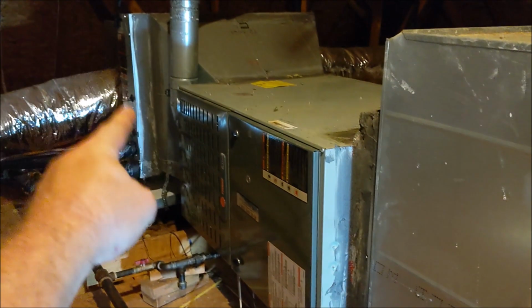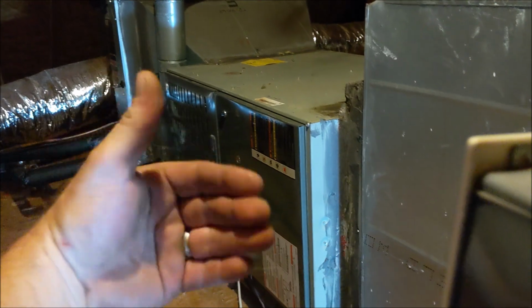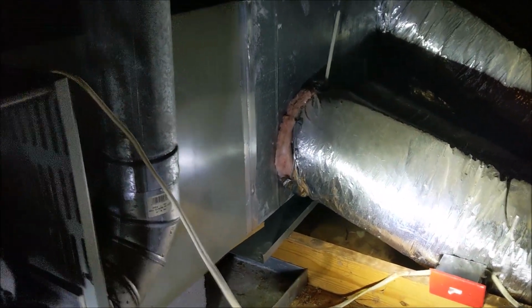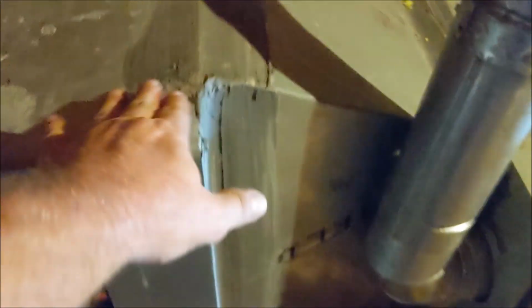The front air supply has a leak in the front where the cold air is leaking out on the supply side, so we do recommend sealing that. They did have tape and mastic air seal, which is that gray stuff. This is the foil aluminum tape, and I'll show you on the other unit. So this is the gray mastic, and they got the foil tape and they put the gray mastic, and then they have the duct board here, and as you can see I could just stick my fingers in there and the air is coming out here nice and cold.